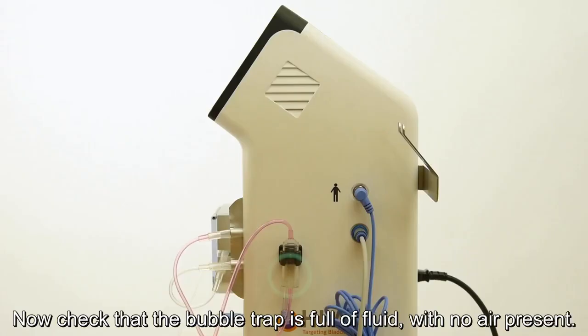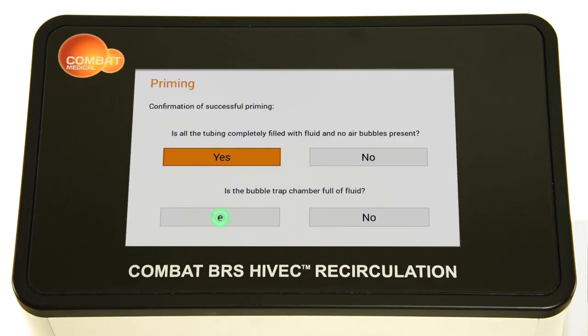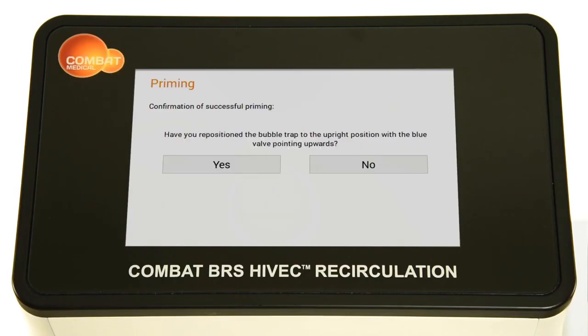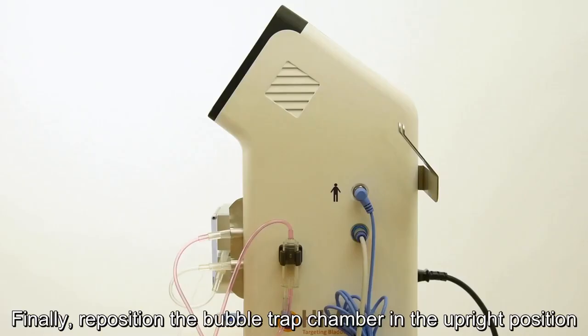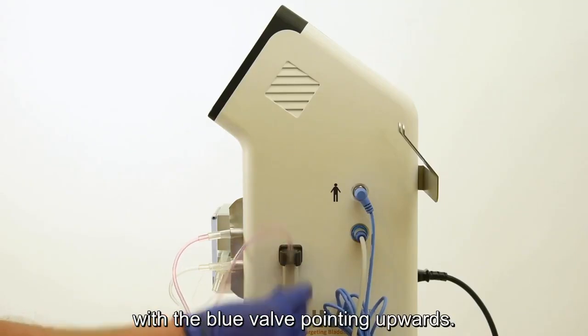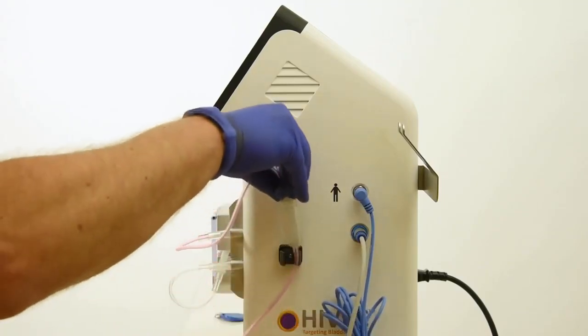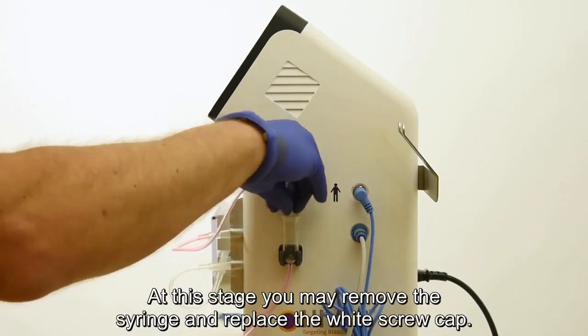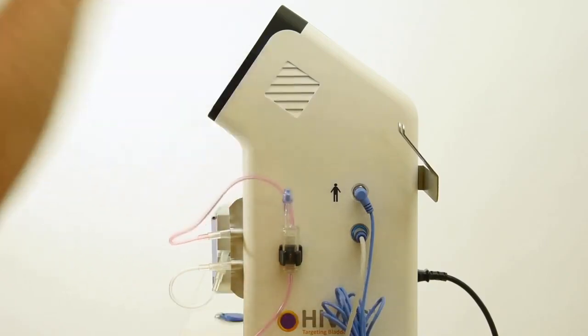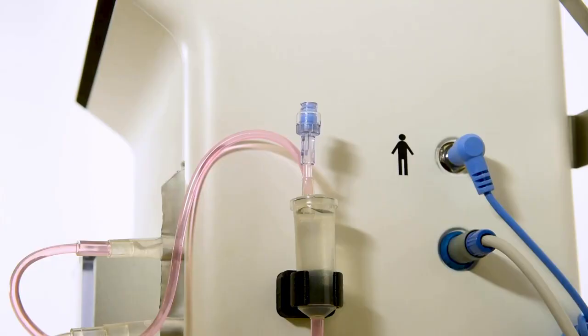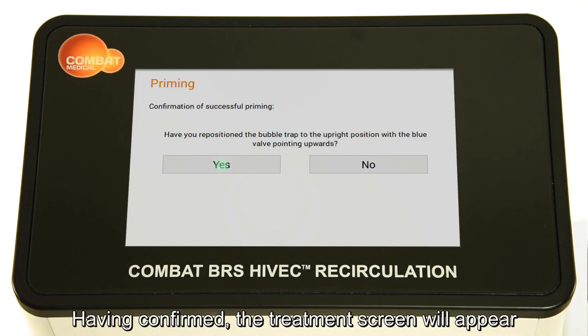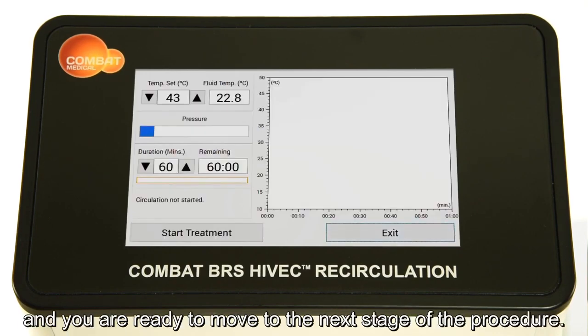Now check that the bubble trap is full of fluid with no air present, and confirm. Finally, reposition the bubble trap chamber in the upright position with the blue valve pointing upwards. At this stage, you may remove the syringe and replace the white screw cap. Having confirmed, the treatment screen will appear and you are ready to move to the next stage of the procedure.